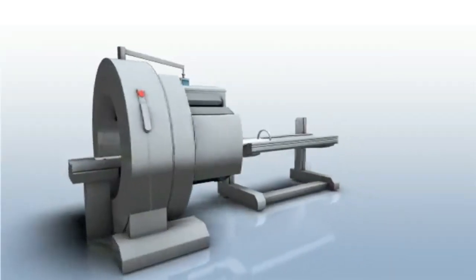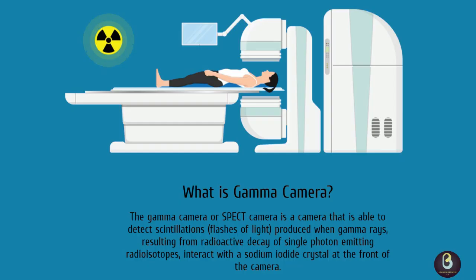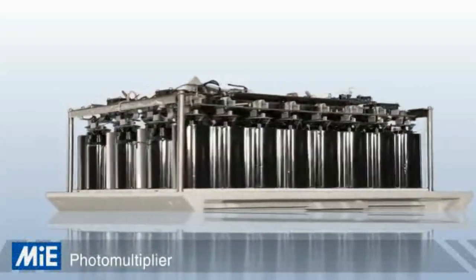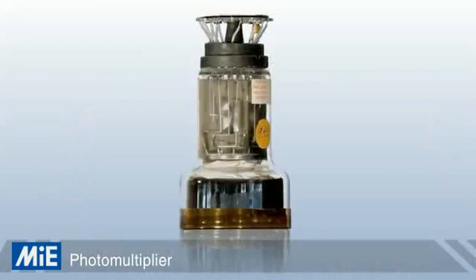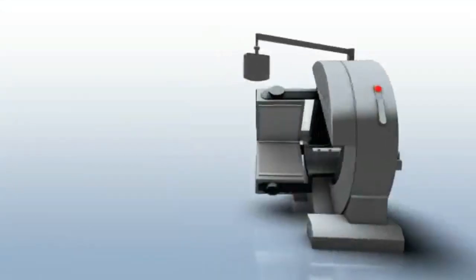So what is a gamma camera? In layman's terms, the gamma camera, or SPECT camera, is a camera that is able to detect scintillations, flashes of light produced when gamma rays, resulting from radioactive decay of single photon-emitting radioisotopes, interact with a sodium iodide crystal at the front of the camera.